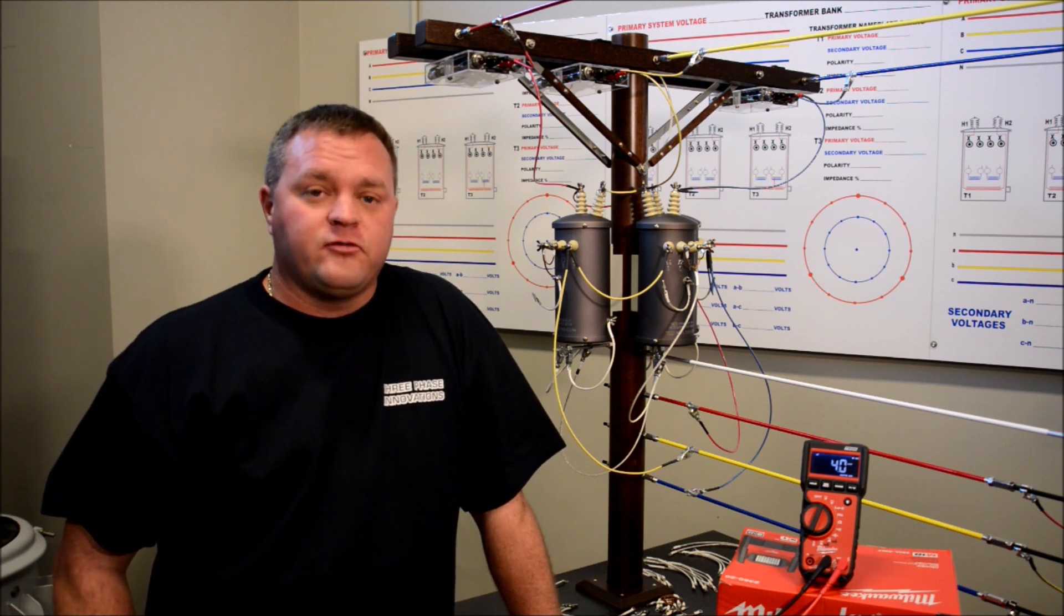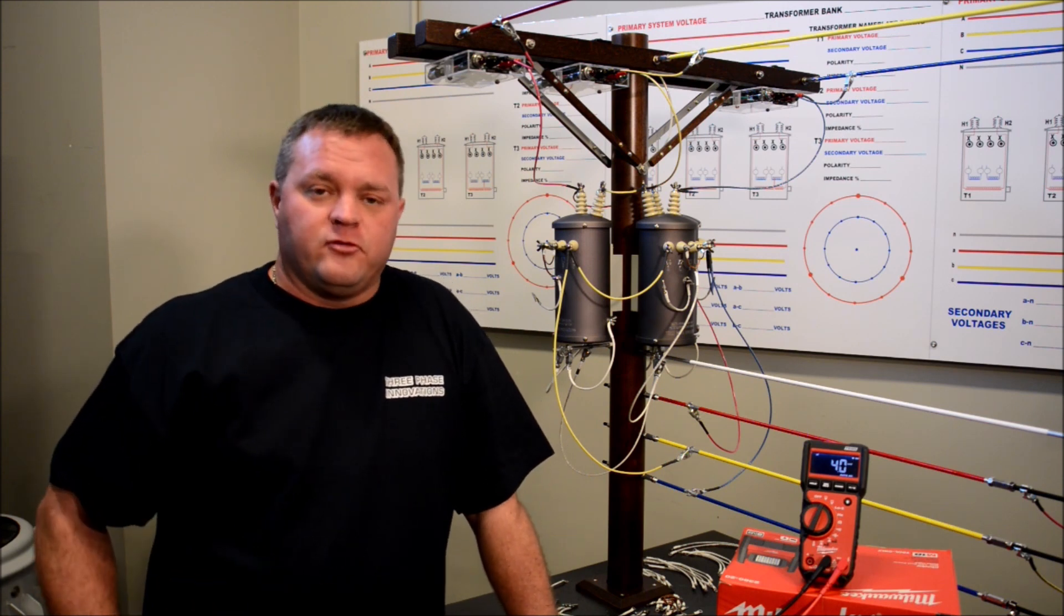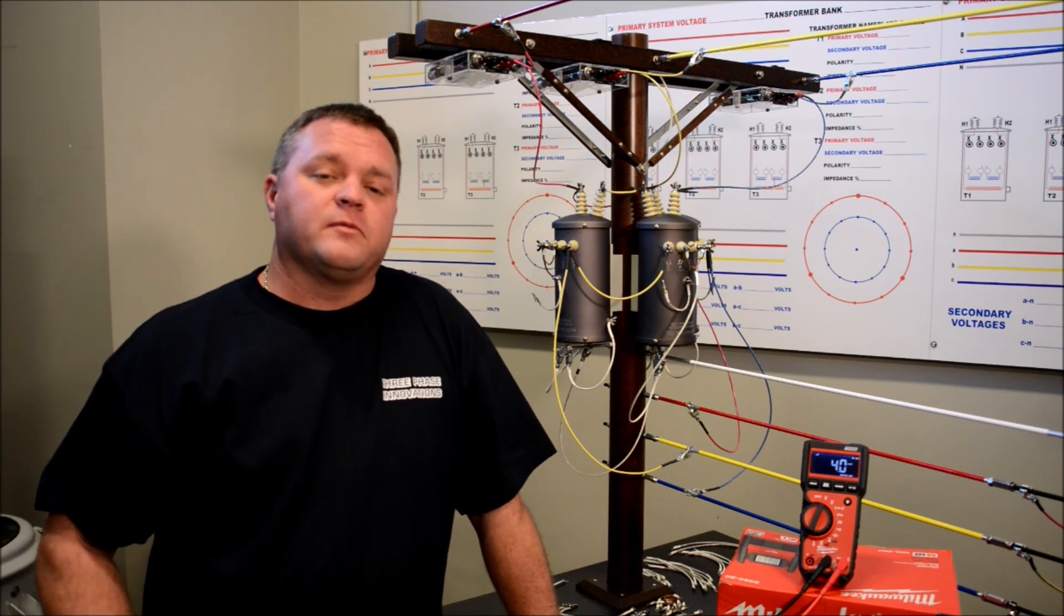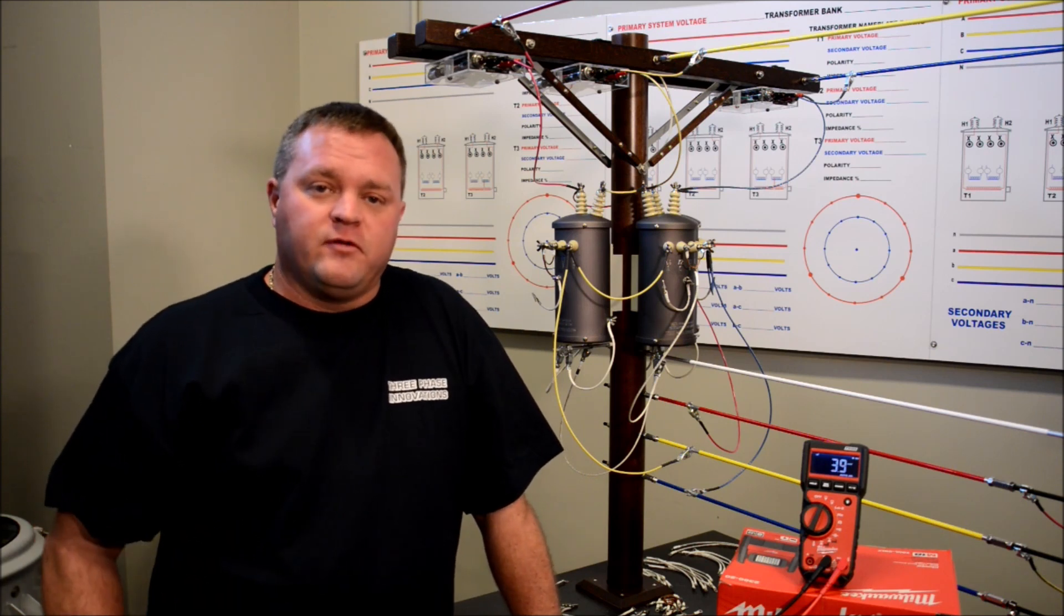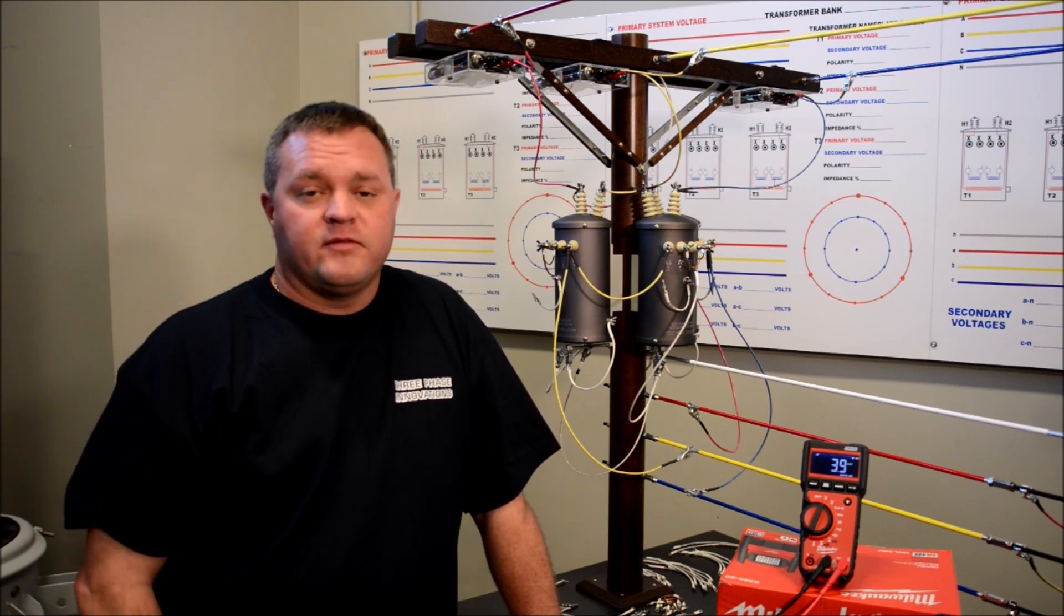Keep in mind this bank also has a 208 high leg. Why is that important? We need to know where that high leg is because if we were ever to change the bank of transformers out for any reason, we need to know where that is because we don't want to put 208 volts on a 120 circuit. If that happens we're going to burn everything up on that circuit.